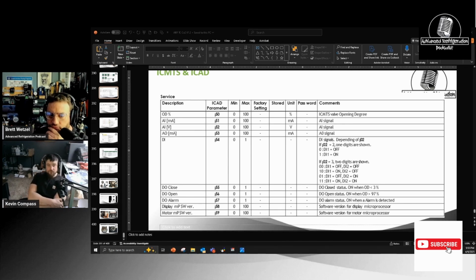And then just keeping those valves clean, like once a year, maybe once every 2 years. If it's not a dirty rack, if it's got stainless piping in it, like good luck. You might as well just order an entire pack of rebuild kits or the O-ring kits, because you're going to be cleaning that nonstop. Especially if they didn't purge when they did the stainless welding, you're going to have sugar dust all over that thing. You keep saying sugar dust, and that's what I refer to it as, but I don't remember exactly what it actually is. It's slag. That's all it is. Okay. Right. It's just welding slag, but I've always heard everybody call it sugar dust because it's like a fine brown powder.